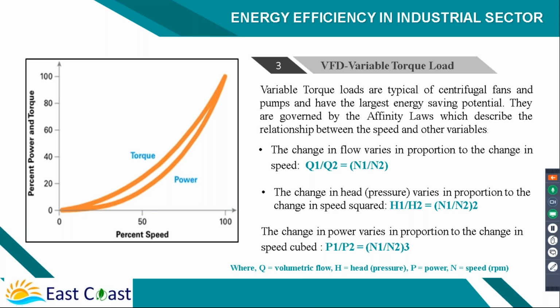Next come the VFDs. Many people in industry know that VFDs can be applied to variable torque load applications like pumps and fans, where maximum saving is possible, because this variable torque equipment follows what is known as the affinity laws. If you want to regulate your flow, it is directly proportional to the speed. You regulate the speed by changing the frequency of the electricity fed to the motor using a VFD, and the flow will change proportionately, and commensurately the head and power also change. Head will change with the square of the flow, so there is much more reduction. And power will change with the cube of the speed.